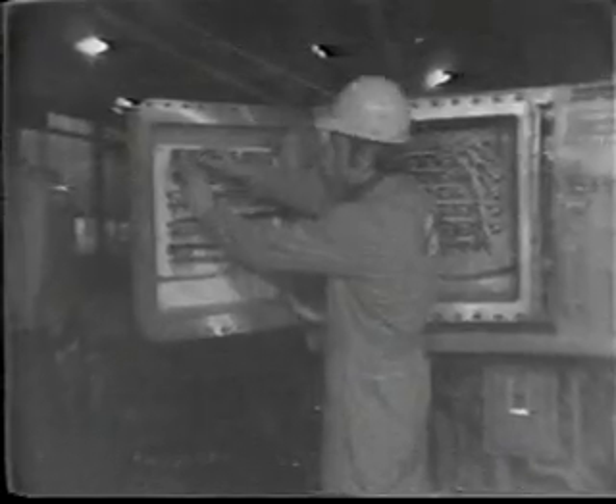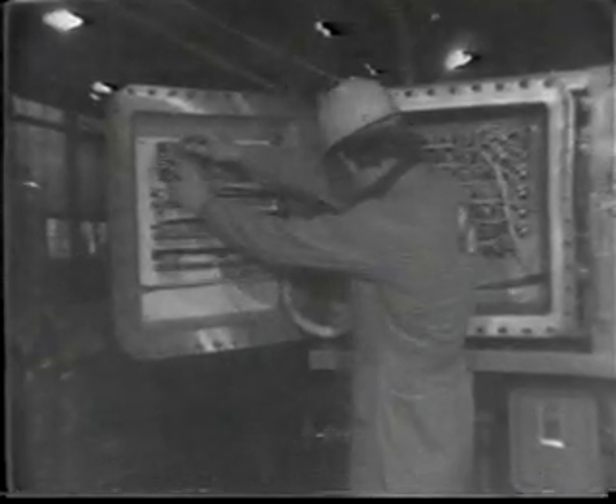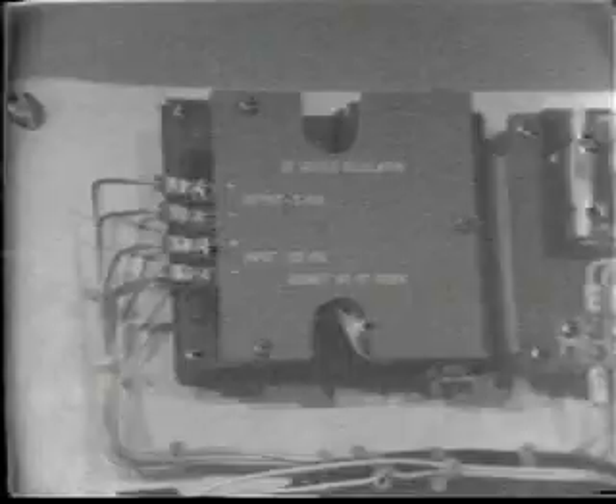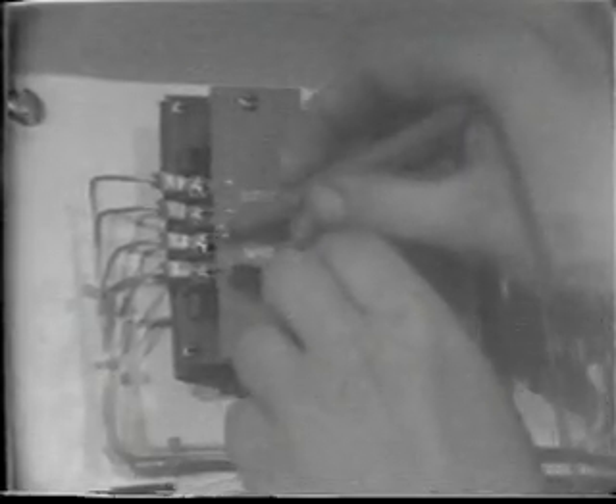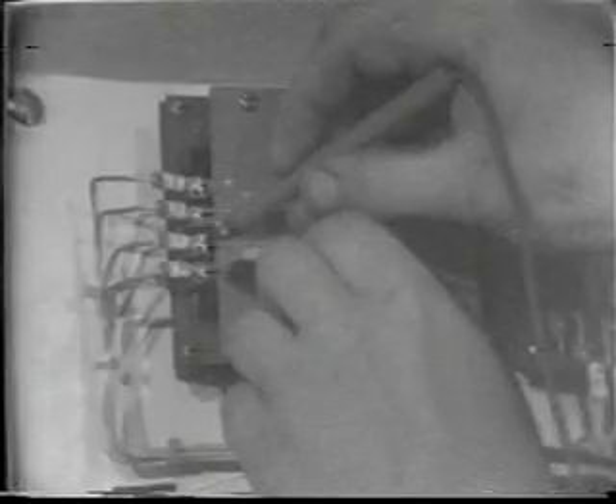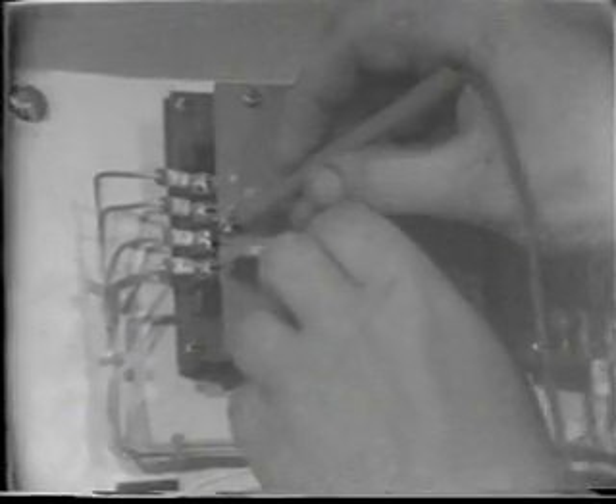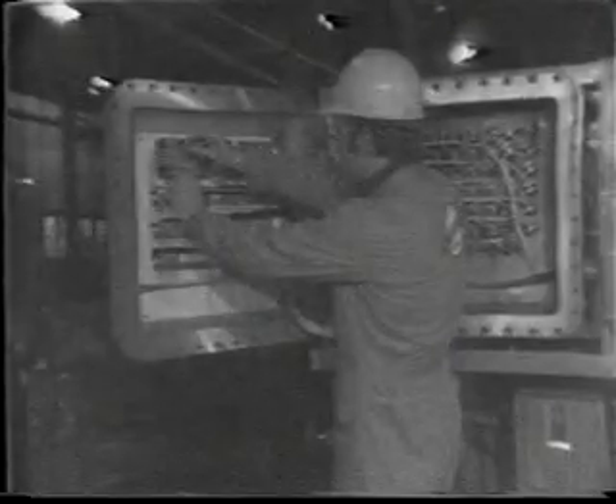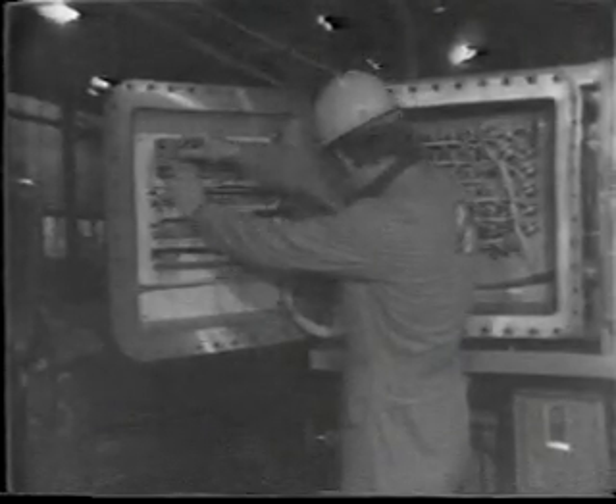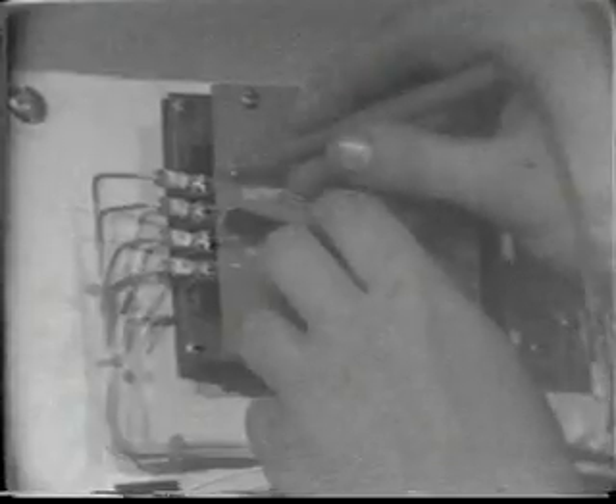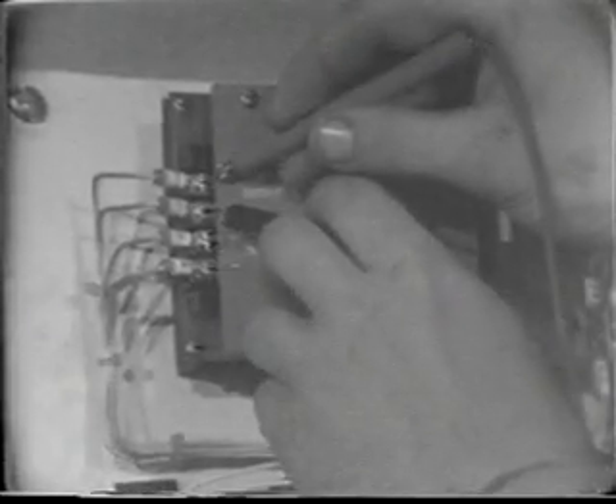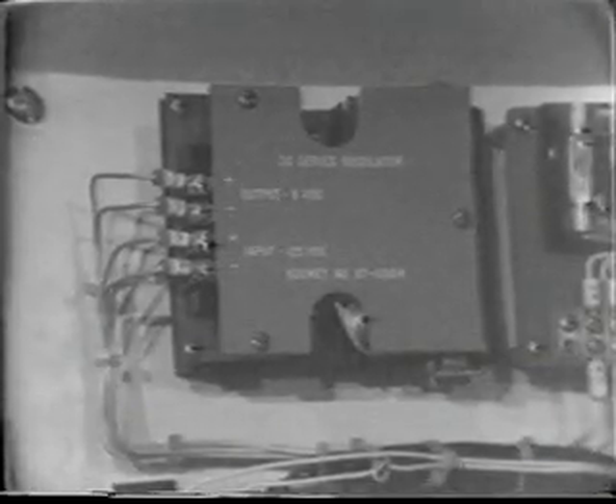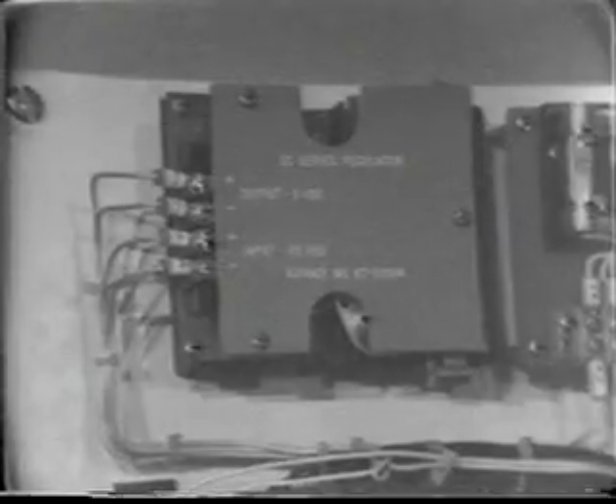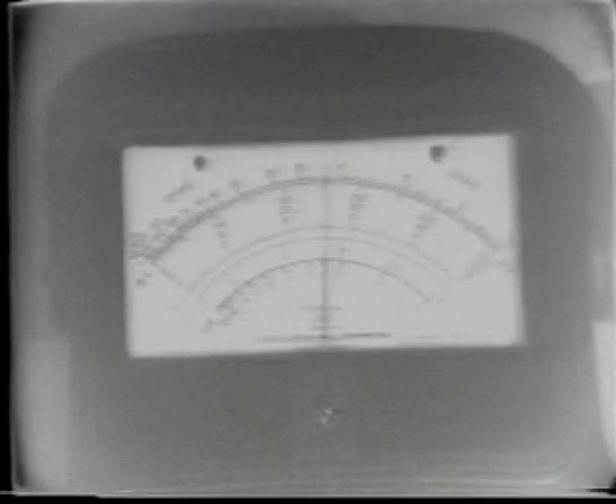Second, if all of the meters on the panel are reading incorrectly, then check the voltage for the system. There is a regulator power supply in the left-hand junction box that supplies voltage to the transducers. The cover plate on the power supply will tell you what this voltage should be. Use your voltmeter and measure the output voltage to be sure it is correct. If the output voltage is not correct, then check the input voltage. If these voltages are both correct, then the meters should read correctly. Adjust the trim pots and recalibrate the meters.